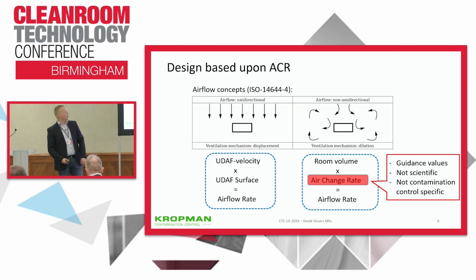If we look at the design of clean rooms, you can distinguish two types of airflow concepts. The left one is the unidirectional airflow concept, which is based on the ventilation mechanism of displacement. The other one is the non-unidirectional airflow concept, which is based on the principle of dilution. In my presentation today, I will focus on the non-unidirectional airflow clean rooms. The airflow rate is mainly calculated by multiplying the room volume times an air change rate.